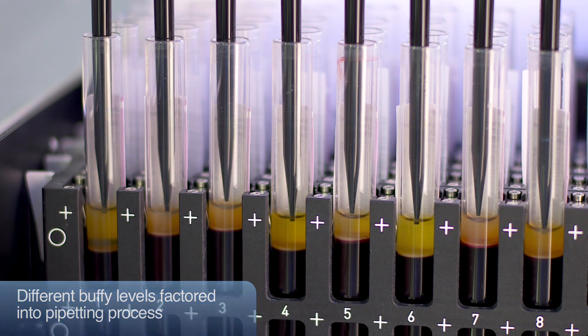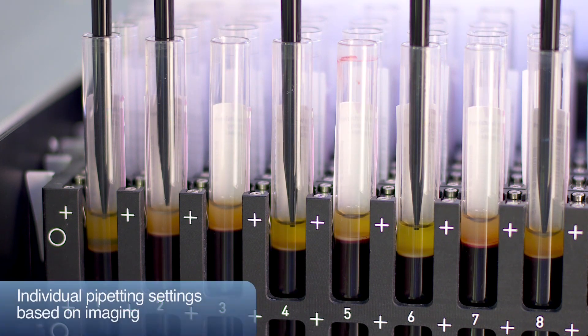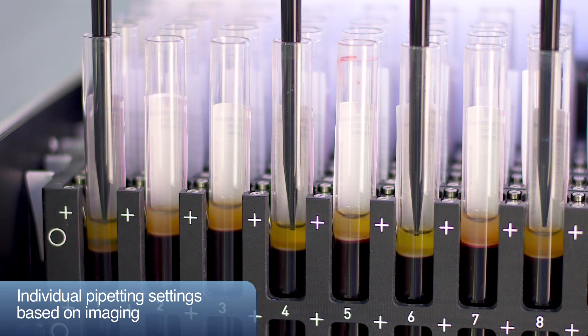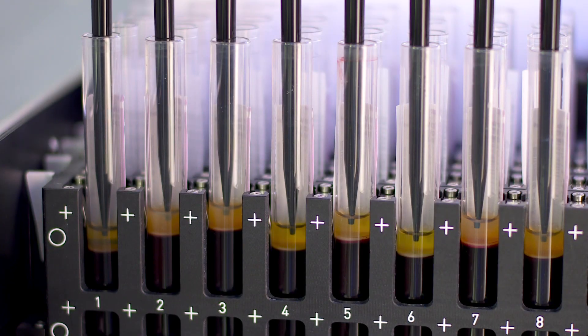The results of the buffy coat detection are used in the pipetting steps to protect the buffy layer. Every sample is pipetted with its dedicated settings to maximize the pipetting accuracy and buffy coat recovery rate.